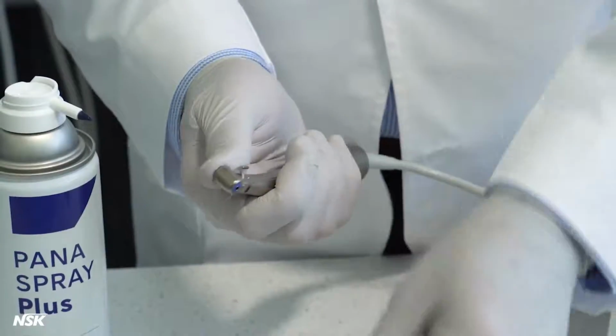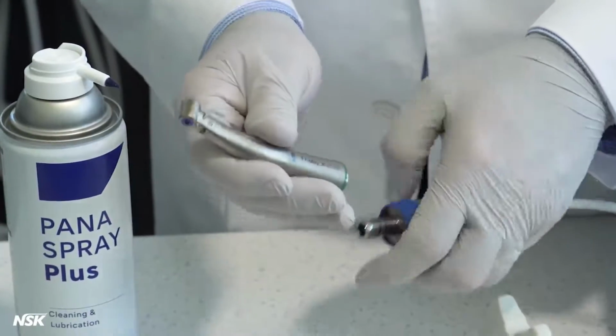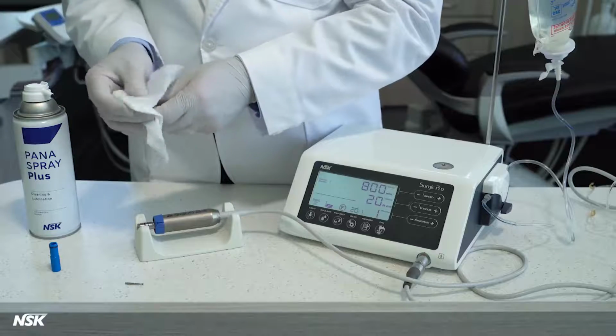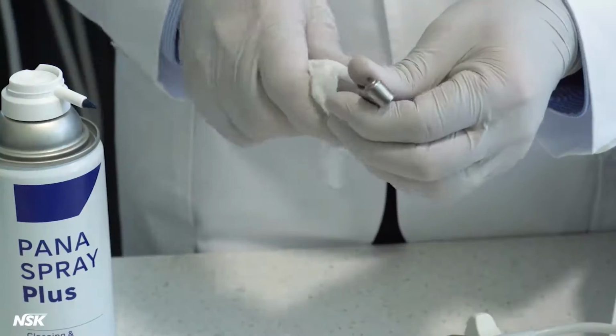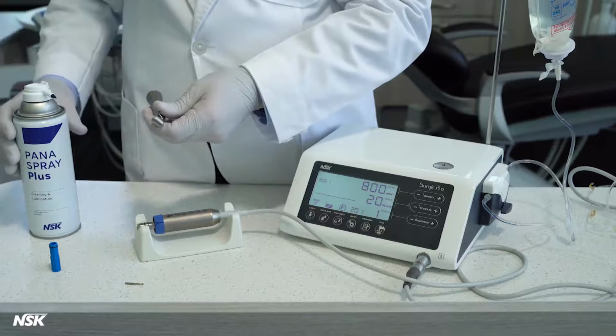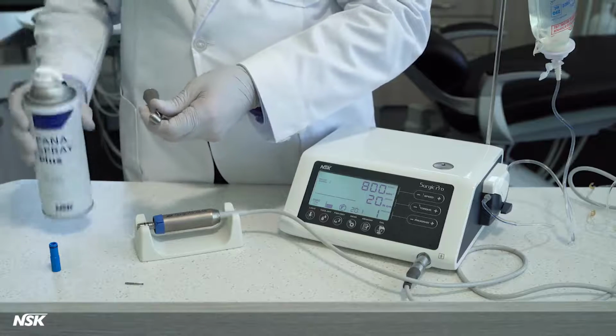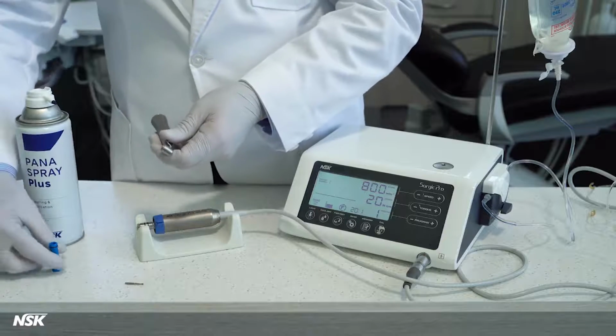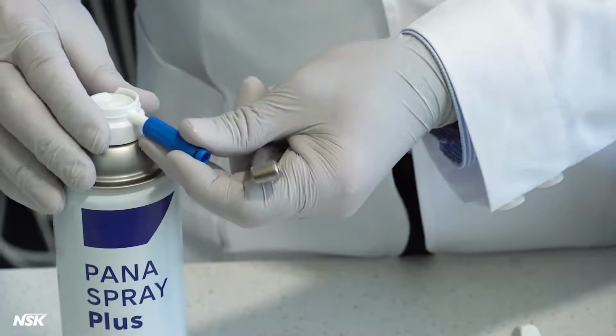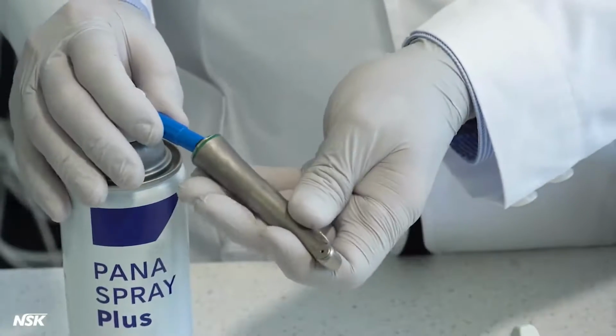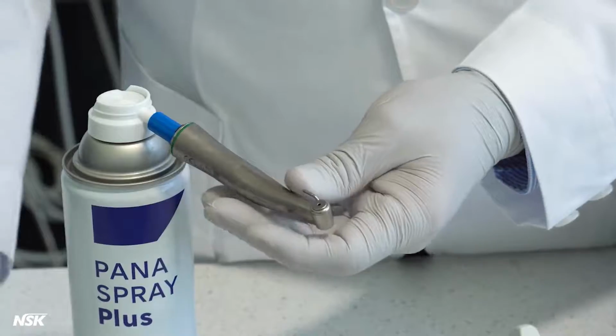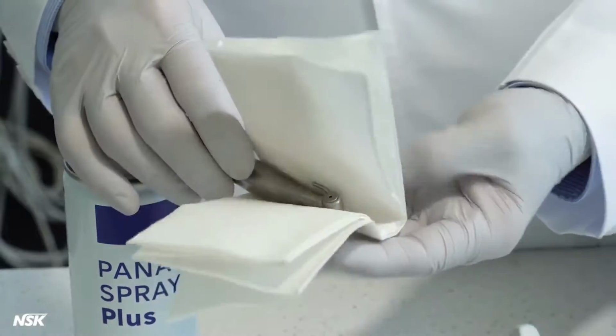Remove the drill. Pull the attachment gently out of the motor. Clean the external surface of the attachment using a cleaning wipe or alcohol. Shake the oil can for 3 or 4 seconds, keeping it in an upright position. Insert the E-type nozzle adapter to the back of the attachment.